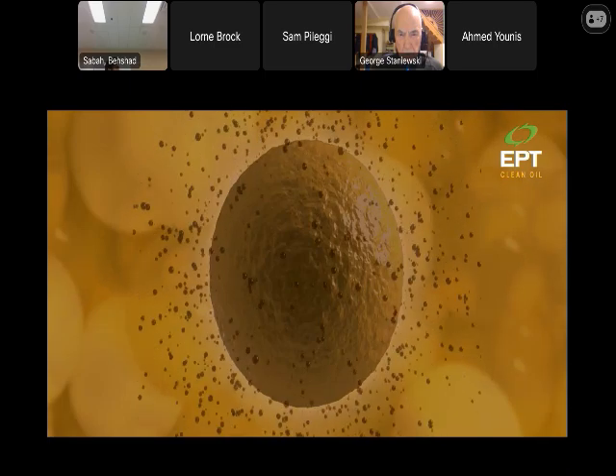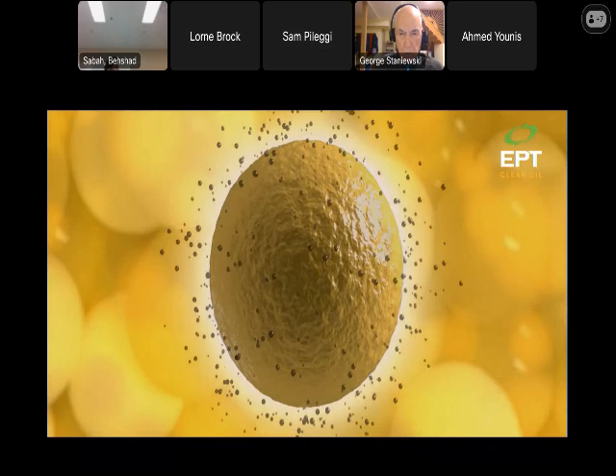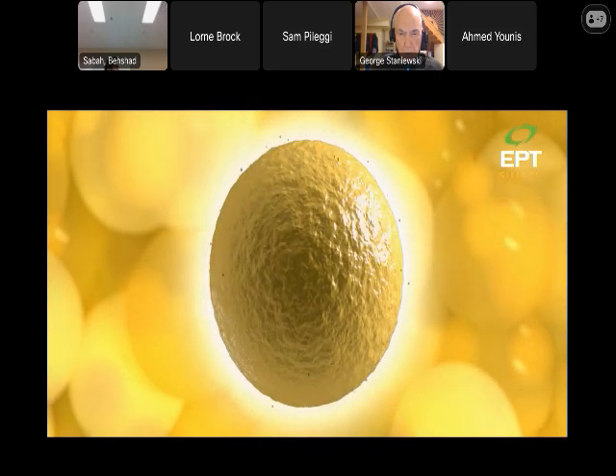I'm going to push one more. There you go. So the ion exchange resin is sacrificial surface area that's really easy to change. Electrically, the contamination in the oil is more attracted to the ion exchange resin than it is to the oil. So as long as this is in the circuit, that oxidation material can't form on a mechanical surface. It has to go here first.